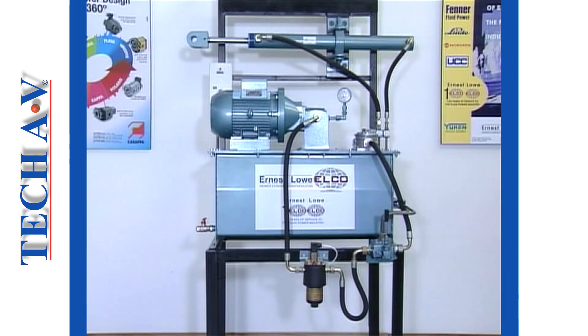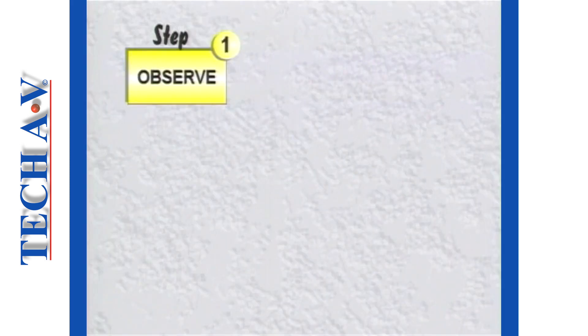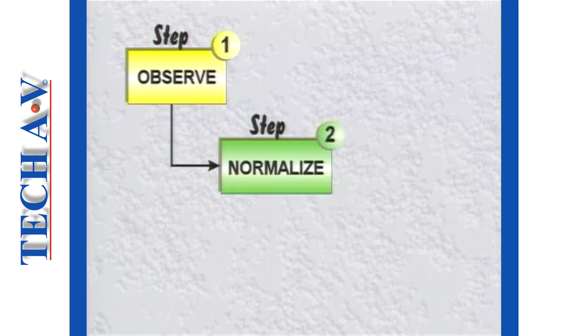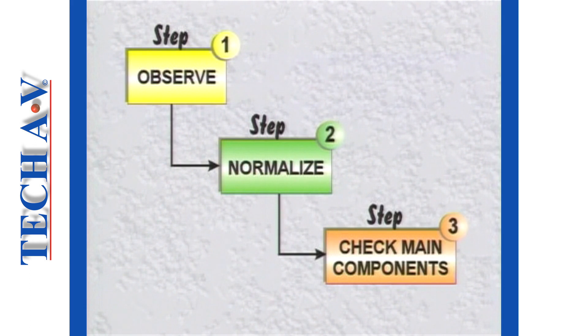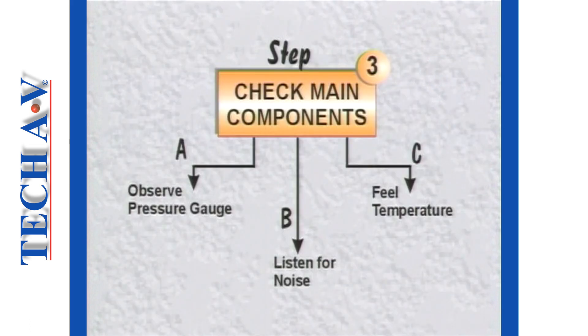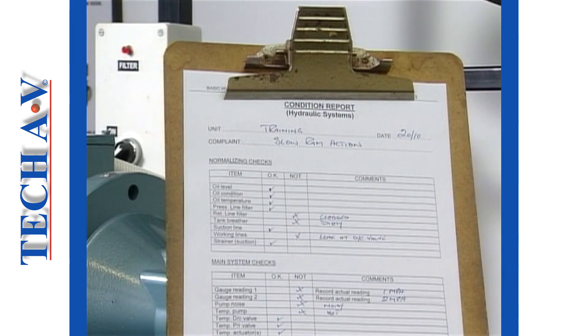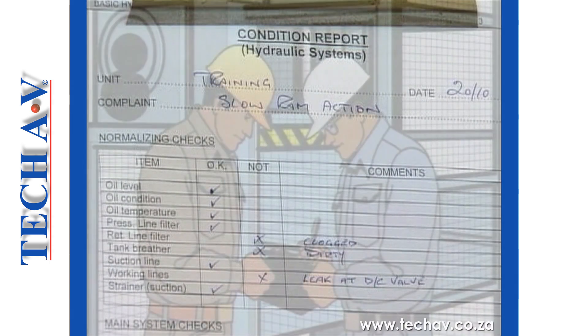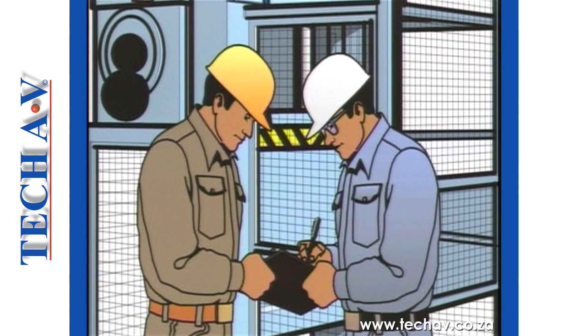Let us summarize the procedure for dealing with faults. First, we observe the problem in order to describe the symptoms accurately. Next, we perform all the normalizing checks to ensure that we do not overlook obvious faults. If normalizing does not solve a problem, then we check the major components and system operation by first observing and noting the behavior of the system pressure gauge, secondly listening for excessive or unusual noises in the pump, and finally feeling each major component for excessive temperature. Having completed your inspection, you should next report your findings to your supervisor, so that the necessary arrangements can be made for repairs to be carried out.